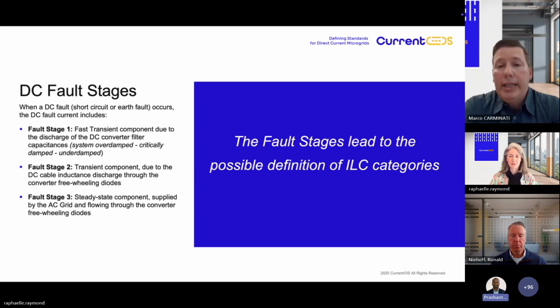Instead, if the system is underdamped, according to the ratio, as I said, between DC capacitances and inductances, we can have that the current waveform can oscillate, and as soon as the voltage on DC side reaches a negative value, basically it is clamped by the freewheeling diodes inside the AC-DC converter, and in that case we start the fault stage 2, which is basically a discharge of the energy inside the inductances of our system through the freewheeling diodes of our AC-DC converter. When the inductances are discharged, then according to the internal architecture of our interlink converter, we can have the third stage, which is a steady state stage. Basically, it is a contribution to the DC fault coming from the AC side, in particular from the AC utility.